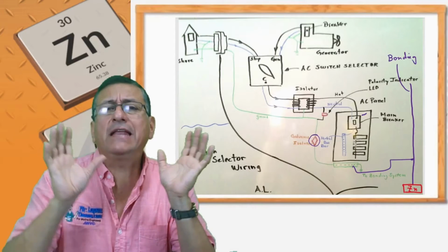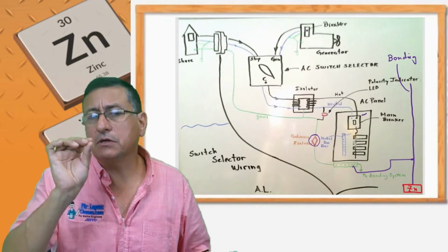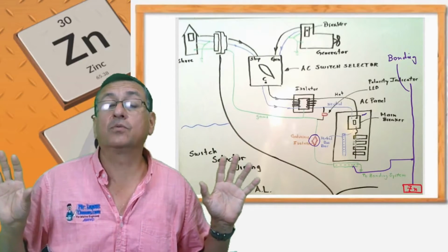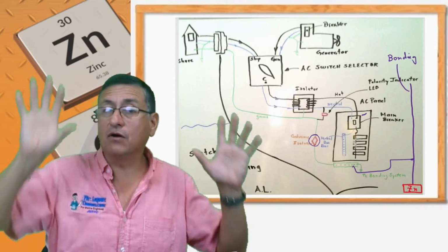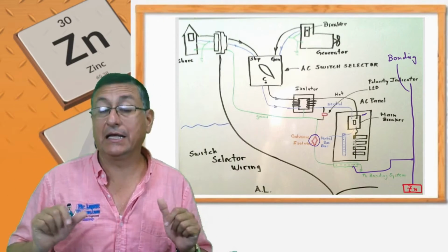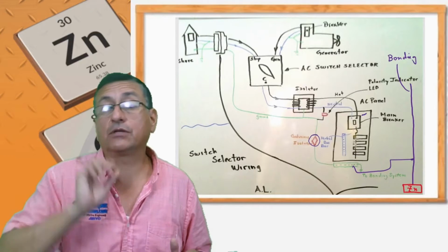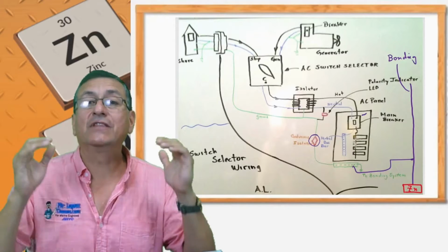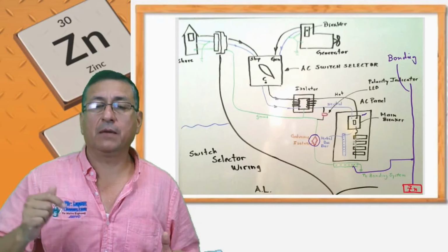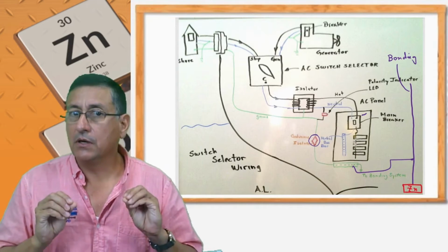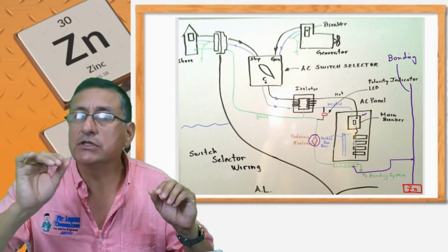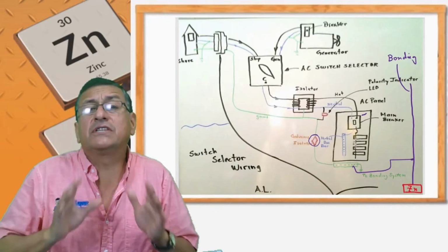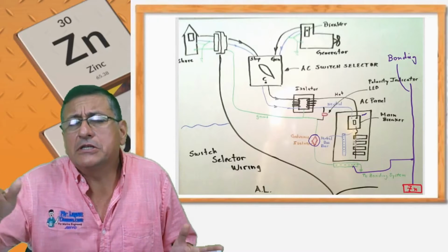If you have leaks in your home or in your building, it's because some equipment is working badly, or the winding of that equipment is not good. We are going to analyze that later. For that reason, you have small currents flowing constantly through the ground. This is the topic of this episode and the next coming episode: analyze where the leaks are. Where is that small constant current coming from? Through the ground, to the grounding system, normally you have 0 or 0.0 something.